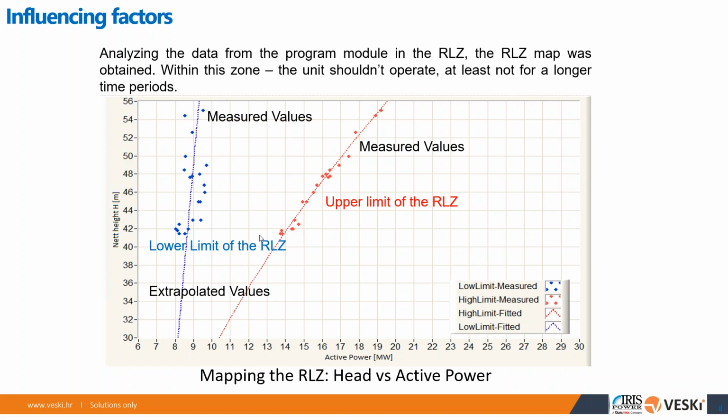So it's a process of collecting the data and analyzing the data, because you need to get all these conditions. You can only have that if you leave the machine operating normally throughout the year, and the water goes up and down, the lake is filling up. We did this by analyzing the data when the low frequency starts to occur in the combination of head and power.